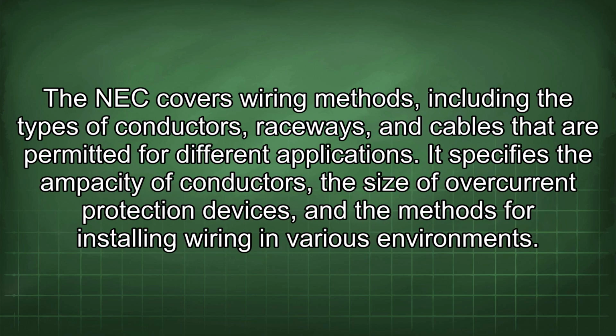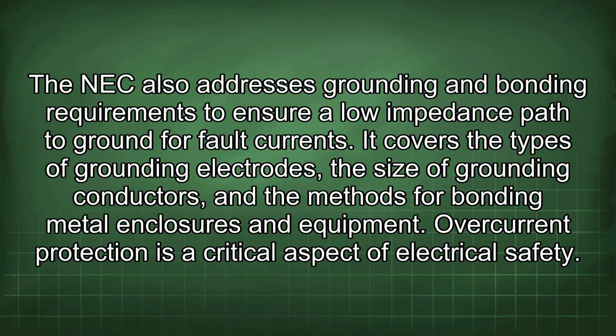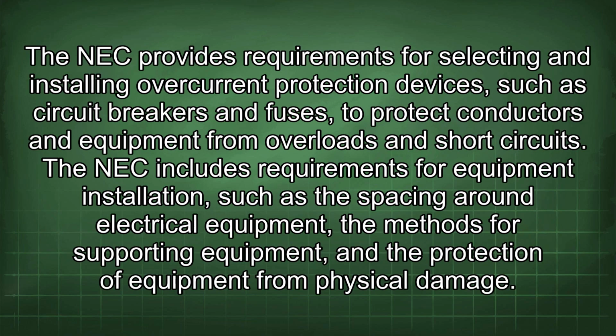The NEC covers wiring methods, including the types of conductors, raceways, and cables that are permitted for different applications. It specifies the ampacity of conductors, the size of overcurrent protection devices, and the methods for installing wiring in various environments. The NEC also addresses grounding and bonding requirements to ensure a low impedance path to ground for fault currents. It covers the types of grounding electrodes, the size of grounding conductors, and the methods for bonding metal enclosures and equipment. Overcurrent protection is a critical aspect of electrical safety. The NEC provides requirements for selecting and installing overcurrent protection devices, such as circuit breakers and fuses, to protect conductors and equipment from overloads and short circuits.